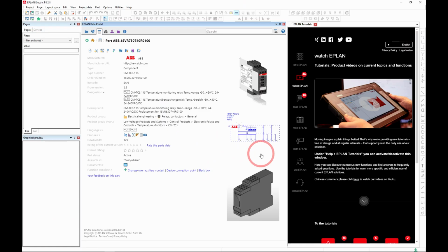When inserting these macros into a project, EPLAN will compare the macro with the project. If the macro contains symbols from a foreign library, EPLAN will ask if you want to swap the macro symbols out with symbols used in the project. In the case of NFPA metric designs, you may need to flip or rotate the macro. In the case of NFPA inch designs, you may need to rotate or flip the macro and resize it.